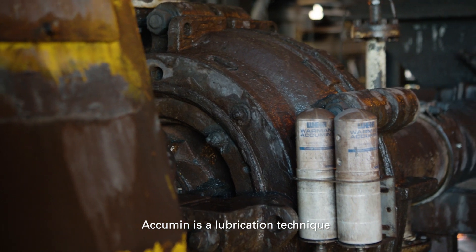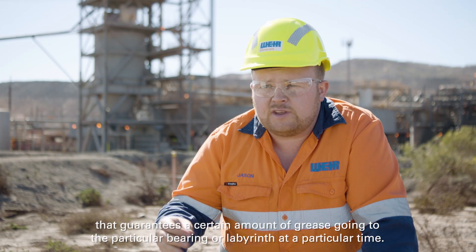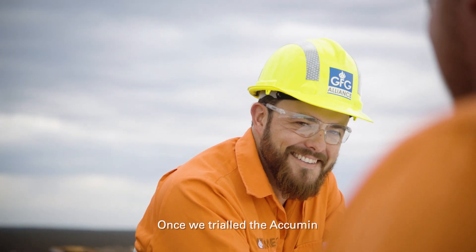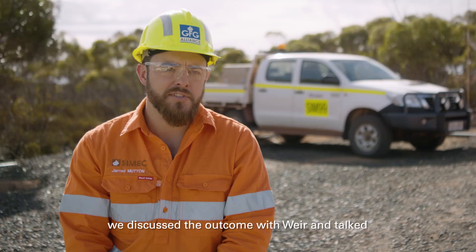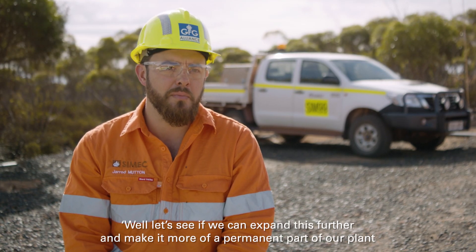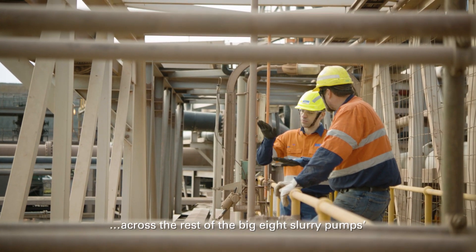Accumin is a lubrication technique that guarantees a certain amount of grease going to a particular part of a bearing or labyrinth at a particular time. Once we tried Accumin on one of our largest pumps and saw the good results, we discussed the outcome with Weir and talked about expanding it further to make it a more permanent part of our plant across the rest of the big eight slurry pumps.